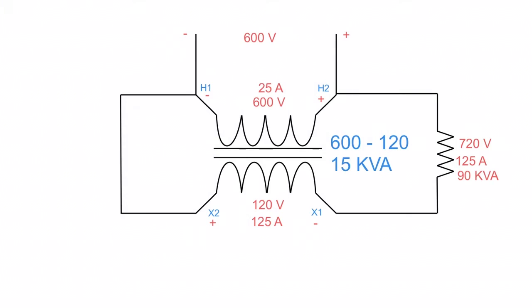With the principle that power in equals power out, if the load is asking for 90 kVA, the line side has to supply 90 kVA. With 600 volts on the line, 90,000 divided by 600 volts gives a line current of 150 amps.